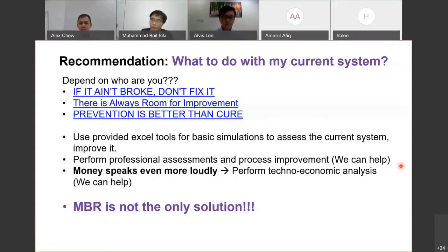Basically they pump a lot of sludge into the MBR tank and take out the permeate. They concentrate the sludge over there, after, let's say, 12 hours of operation, then they return the sludge to the bioreactor, the aeration tank. In that case, yes, it's potentially anaerobic in the MBR tank. I hope that answered.